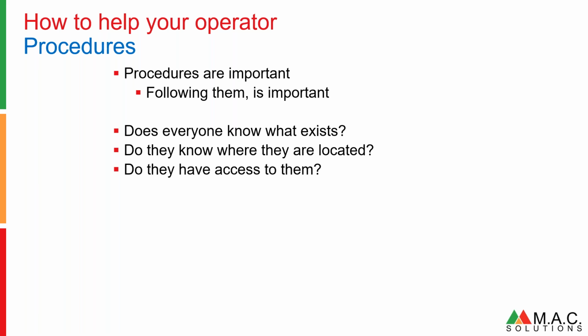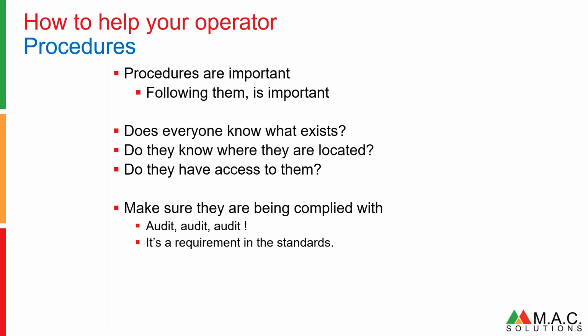While I was talking to the guys, I actually had an operator tell me, this is what we've been told we have to do, which kind of followed the procedure that the engineer at the front of the room had a copy of. Yep, I said, well, that kind of follows in with what you should be doing. When I did the 3rd training course, one of the operators said, oh, I don't do that. It's a lot of hassle when we shelve alarms. Somebody shelves a bunch of alarms on the shift before me. They auto unshelve when I come onto shift, and I have to deal with a whole bunch of alarms, decide what to do with them.